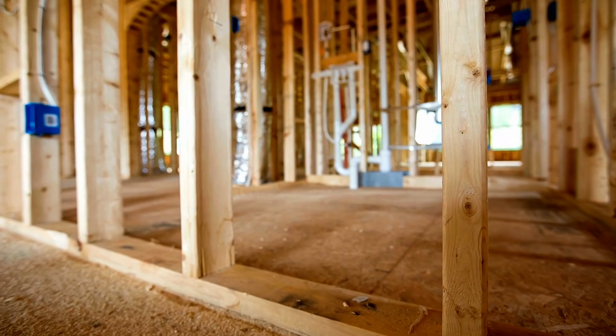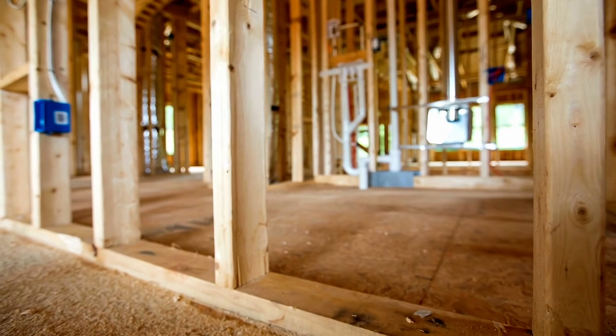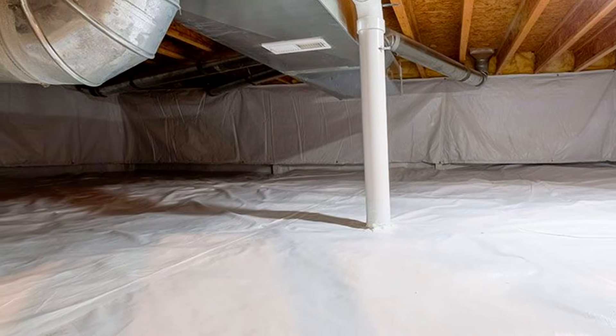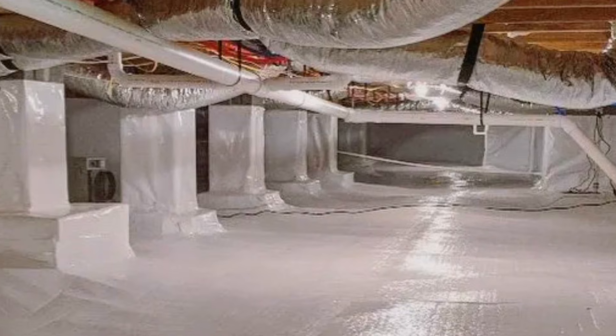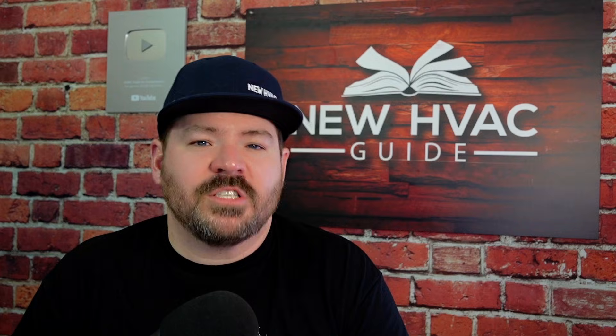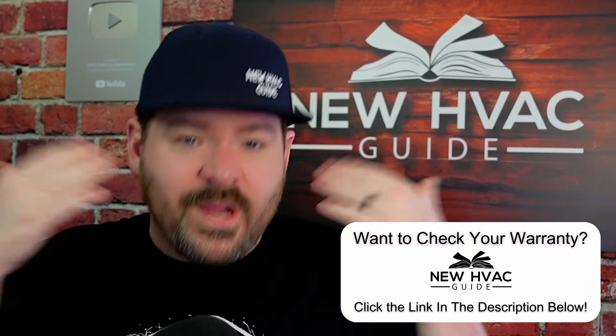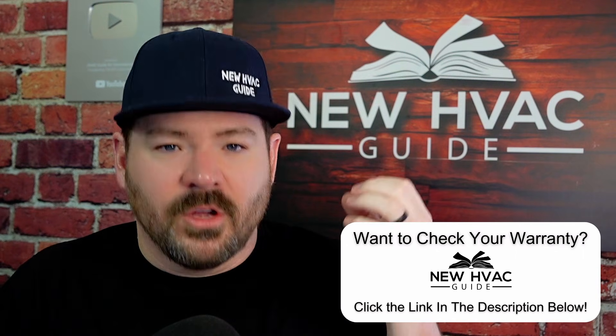A lot of these things in today's home construction are almost taken care of by default. Adding exhaust fans to bathrooms helps make that room negative pressure — you need to use those fans, but just knowing that helps with balancing. But understand you don't want to add a duct to a crawl space and blow air in there without some way of sealing. If you're going to condition the crawl space, you want it sealed and the humidity right, because making that area positive pressure could push musty odors and contaminants to the rest of your home.